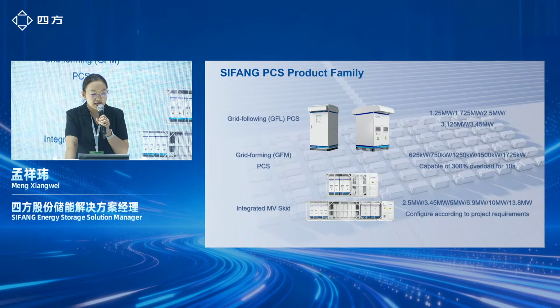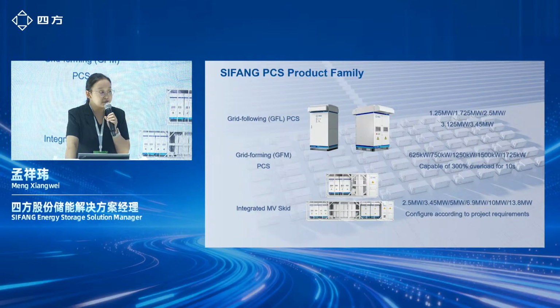For our PCS products, we focus on the centralized PCS, and our grid-following PCS covers rated capacity from 1.25 megawatts to 3.45 megawatts. All the models comply with the IEC standards. Also, we have the grid-forming PCS, whose capacity covers from 625 kilowatts to 1,725 kilowatts and is capable of 300% overload for a short term. We can also provide the integrated medium voltage skid, which includes the PCS and the transformer, with capacity from 2.5 megawatts to 13.8 megawatts.